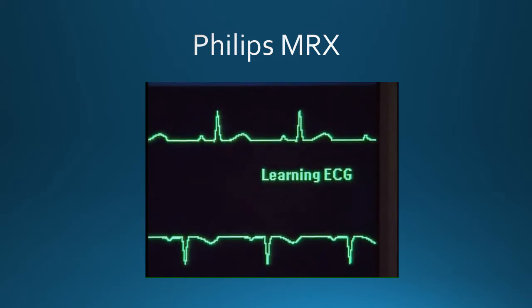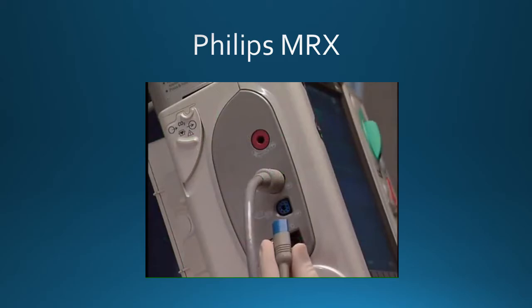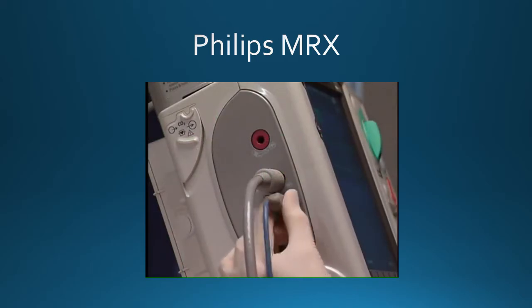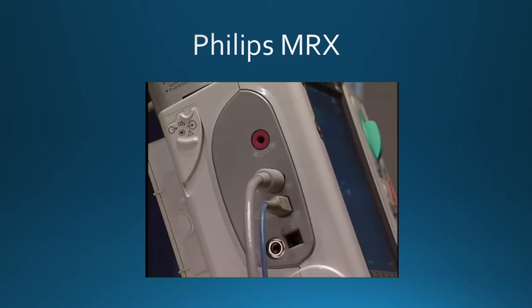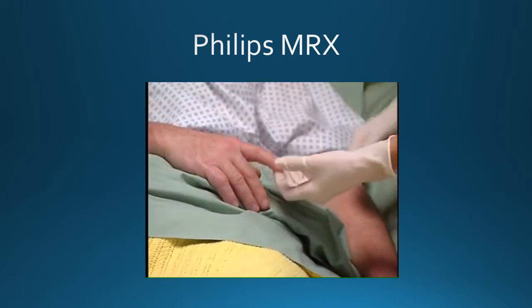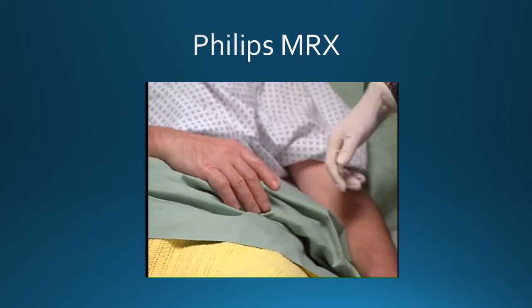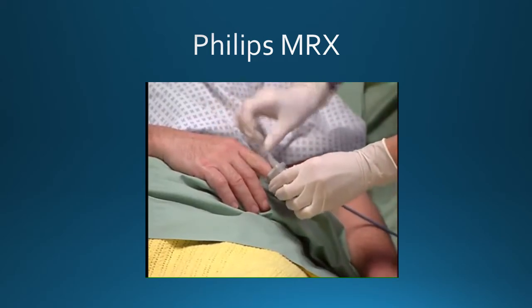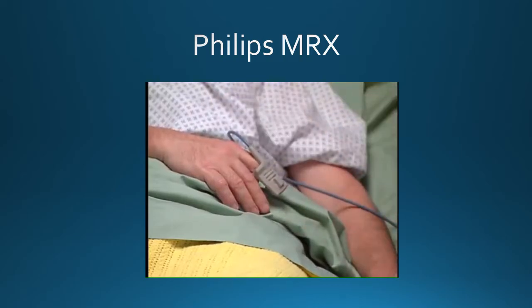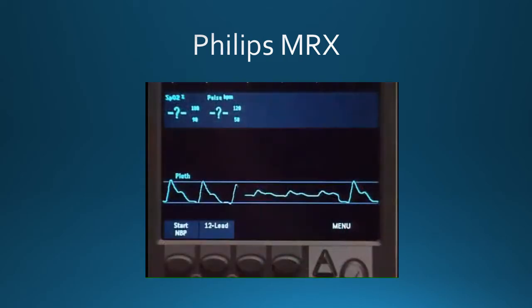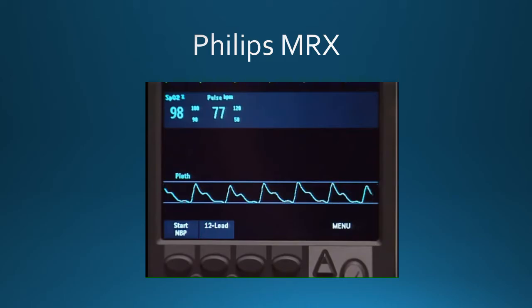Now, let's set up SpO2 monitoring. Insert the blue connector into this port located on the measurement connector module. When choosing a location for the SpO2 sensor, the most important consideration is to pick a site that is warm and has good perfusion. Apply the appropriate sensor to the patient. A pleth wave displays while the oxygen saturation is measured and the value is calculated. Within seconds, an oxygen saturation reading and patient pulse rate appear. As the patient's oxygen saturation changes, the SpO2 value is updated continuously.